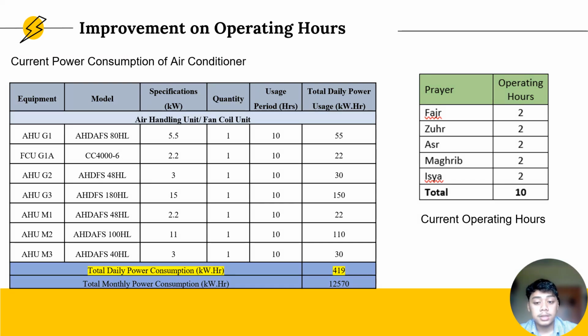As our next improvement, which is on the operating hours of the air conditioner, the current operating hours have a total of 10 hours. We aim to reduce the operating hours to only 8 hours. This is due to every prayer not taking more than 1 hour. Therefore, reducing the operating hours is an alternative that can be implemented in enhancing the energy consumption for the mosque. So we can observe that the total daily power consumption for now is 419 kilowatt hour.